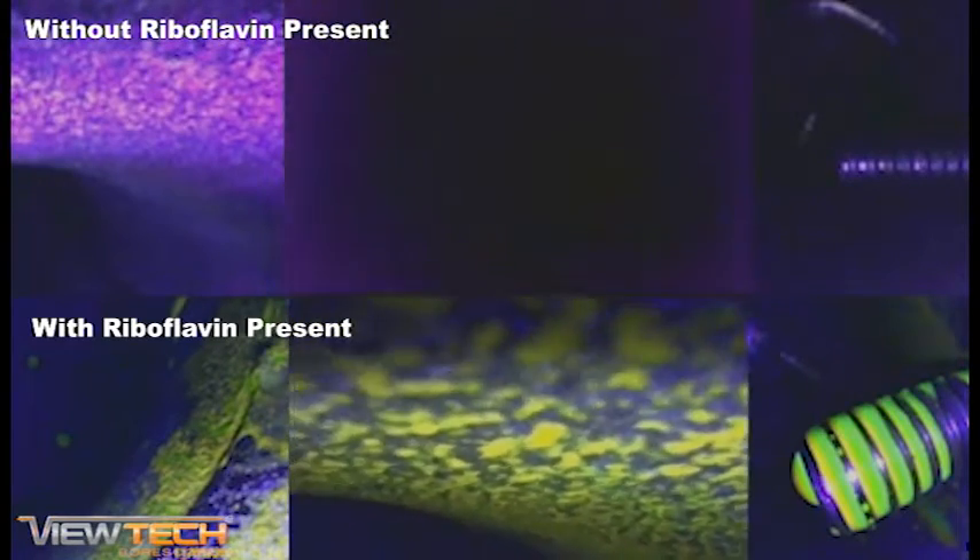Riboflavin testing begins by coating all inspection surfaces with the solution, followed by running the system's cleaning cycle as designed. Next, by utilizing a ViewTech ultraviolet video borescope, remaining visible residue indicates that corrective action must be taken to further diagnose the cleaning spray pattern or coverage issue.